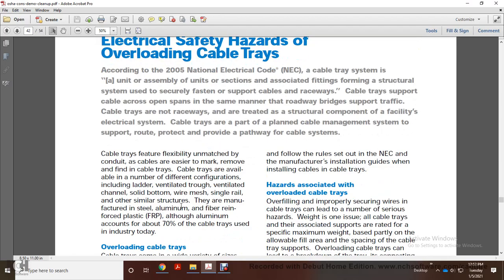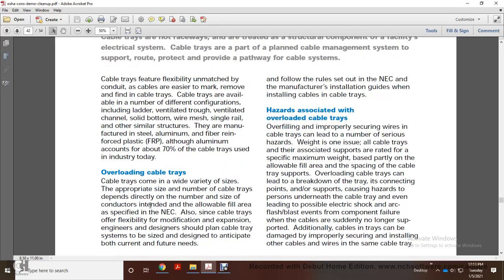Cable trays feature flexibility, unlike conduit, as cables can be added or removed as defined in the cable tray. Cable trays are available in a number of different configurations, including ladder, ventilated trough, ventilated channel, solid bottom, wire mesh, single rail, and other similar structures. They are manufactured in steel, aluminum, and fiber reinforced plastic, although aluminum accounts for about 70% of the cable trays used in the industry today.